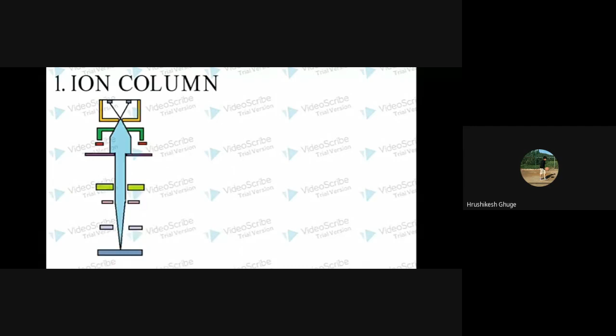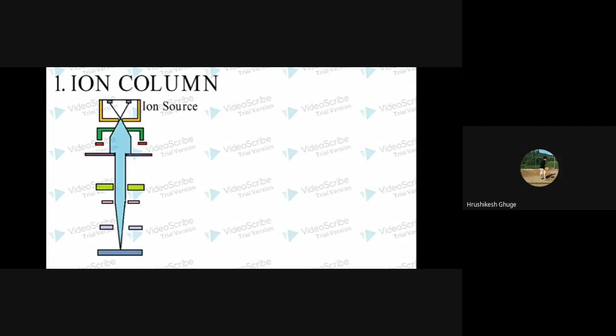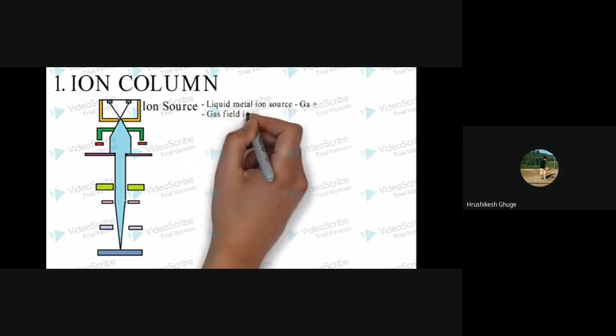This is a general schematic of the ion column. Firstly, it has an ion source for generating the ions. It can be of two types: liquid metal ion source (LMIS) or gas field ion source. Most FIBs use LMIS, which is common and uses gallium Ga+ ions as it has a low melting point. A gas field ion source can generally use hydrogen or helium gases. From the liquid metal ion source, the ions are field evaporated and forced to travel downwards.